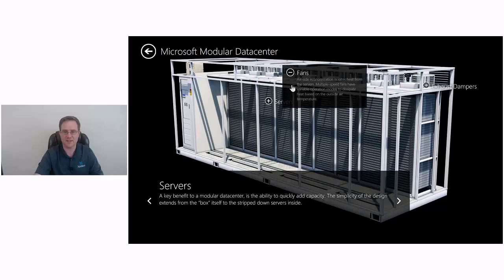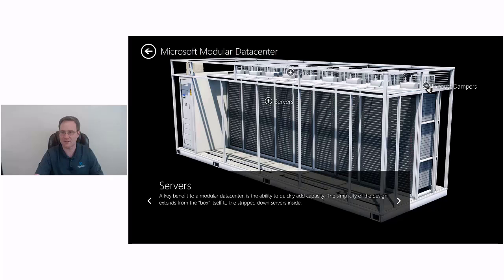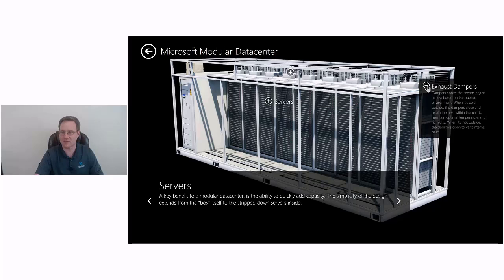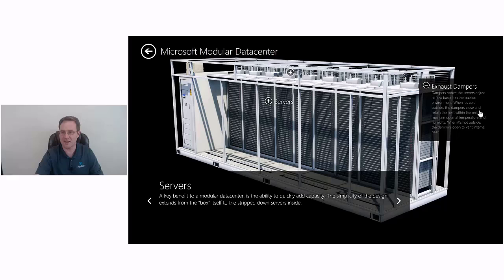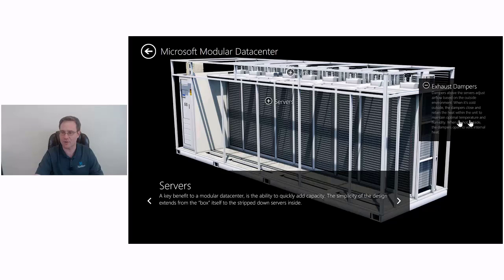The airside economization isolates heat from the servers. Multiple speed fans have variable operation modes to dissipate heat based on the outside air temperature. The exhaust dampers above the servers adjust airflow based on the outside environment. When it's cold outside, the dampers close and retain heat within the unit to maintain optimal temperature and humidity. When it's hot outside, the dampers open to vent internal heat.